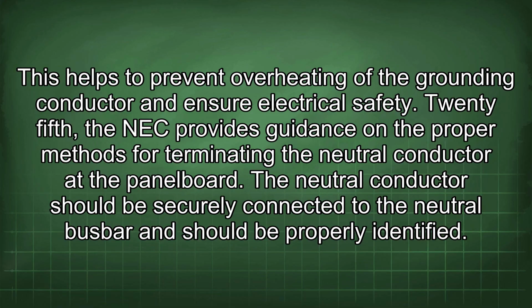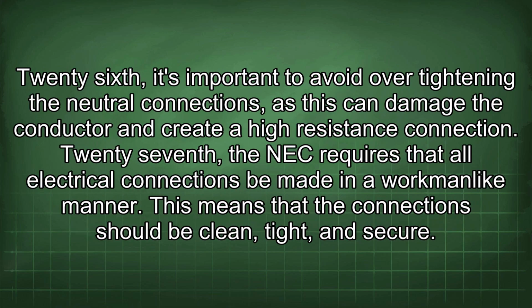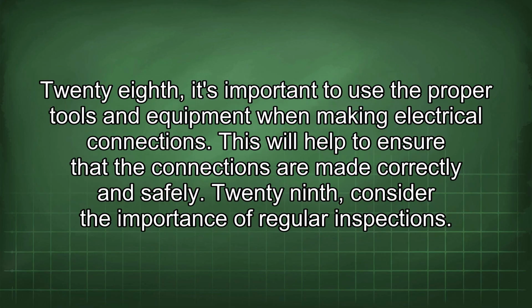25th, the NEC provides guidance on the proper methods for terminating the neutral conductor at the panel board. The neutral conductor should be securely connected to the neutral busbar and should be properly identified. 26th, it's important to avoid over-tightening the neutral connections, as this can damage the conductor and create a high-resistance connection. 27th, the NEC requires that all electrical connections be made in a workmanlike manner. This means that the connections should be clean, tight, and secure. 28th, it's important to use the proper tools and equipment when making electrical connections. This will help to ensure that the connections are made correctly and safely.